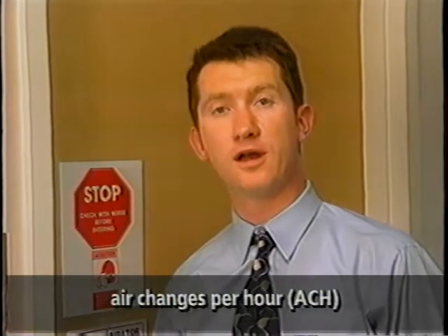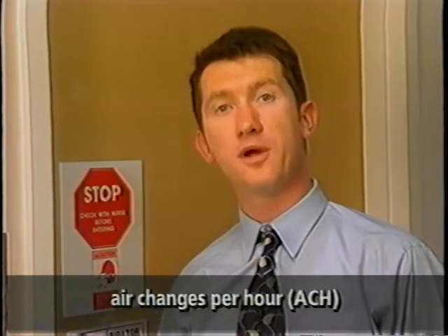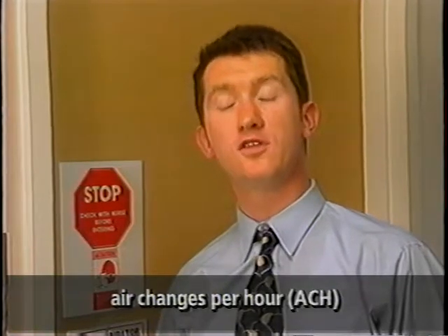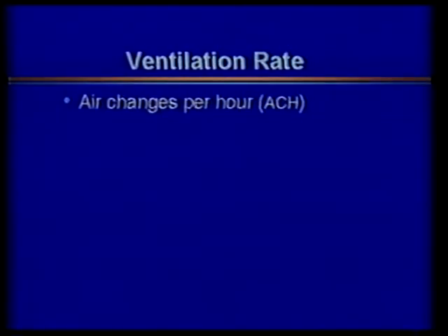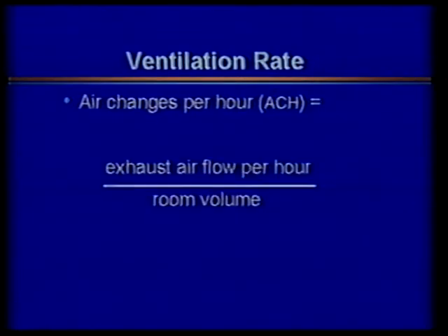The most common way to quantify ventilation is in air changes per hour, ACH, which compares the airflow to the dimensions of the room. The ACH is determined by a relatively simple calculation, the amount of air that is exhausted from the room each hour divided by the volume of the room. The exhaust air rather than supply is used because it is the exhaust that removes any airborne contaminants.